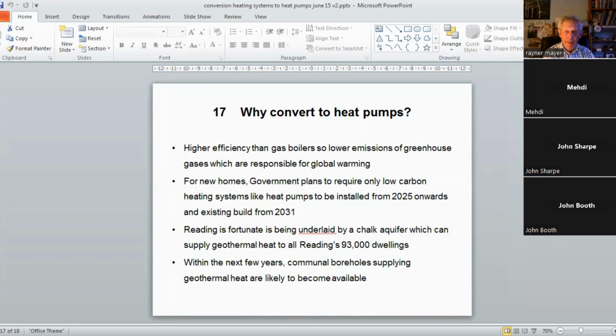Thank you. Let me just summarize. There are costs associated with installing the heat pumps, both in terms of the heat loss of the homes and the actual costs for the heat pumps or air source heat pump. It's clear that air source is cheaper than ground source as far as the developer is concerned. As far as the DNO is concerned, the situation is reversed. The ground source heat pump is much better than the air source heat pump.